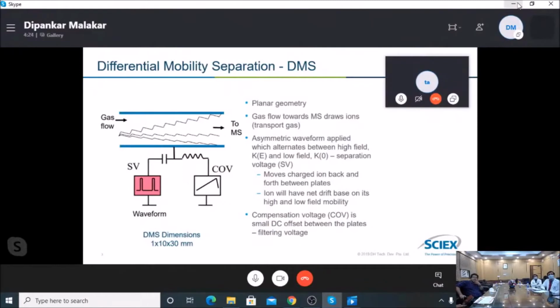An asymmetric waveform is applied, which alternates between high field and low field. It's called the separation voltage. There are two voltages actually applied for separating the analyte: one is called separation voltage, the other is called compensation voltage. The separation voltage fluctuates from high field to low field, and it separates the ions.